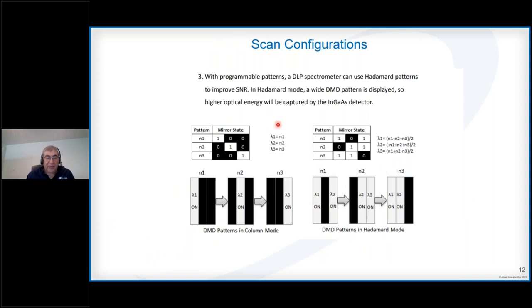Here's a quick comparison of the Hadamard and Column. In case of Column, only one of the mirrors in each column is turned toward the detector, as you can see here. But in case of Hadamard, you have more than one mirror turning towards the detector, so Hadamard will have a higher throughput and would help the signal-to-noise ratio improvement.